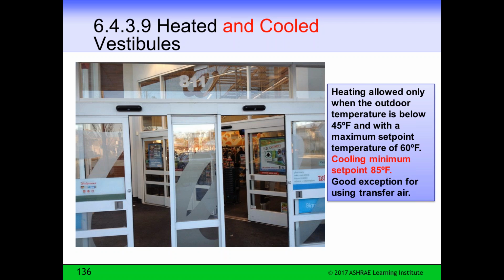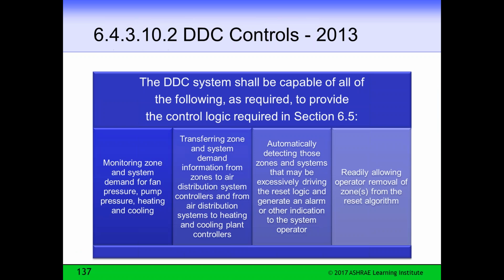Now, we do have a good exception for using transfer air. If you bring air that you were going to exhaust anyway from the cooled and heated part of the building, then we don't have these requirements for minimum and maximum temperature set point at all for the room. So reusing that air and then exhausting it out this way instead of out of an exhaust fan is much better, more efficient, and will make you more comfortable, or your customers more comfortable.